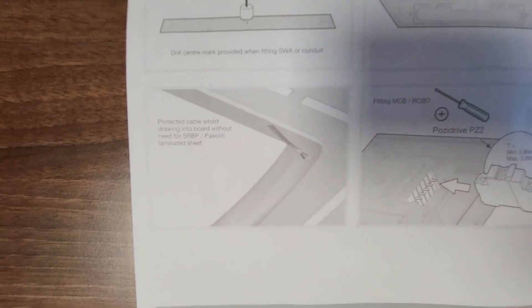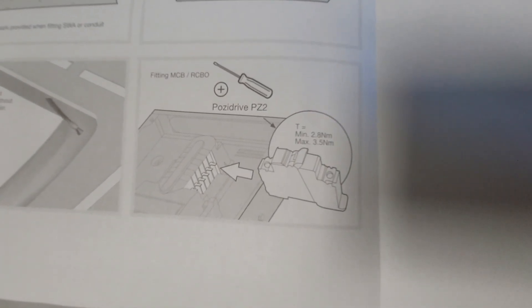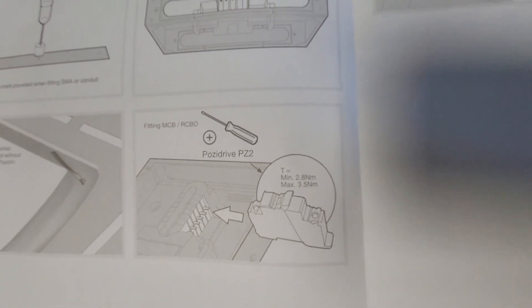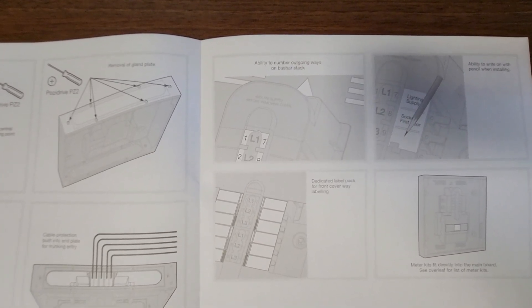The Paxolin laminated sheet is mentioned there. And how to fit your MCBs or RCBOs with the torque values — it actually gives a minimum and maximum range, not a preset target. There is a bit of tolerance in there. So you need to make sure you're using an appropriate torque driver that can achieve those settings. Some of the cheaper ones fall down on the TPN stuff because they don't go high enough, which is why we use Wera. You've then got your ability to number your outgoing ways on the busbar stack, which is always handy so you can give yourself a circuit reference while you're inside the board.